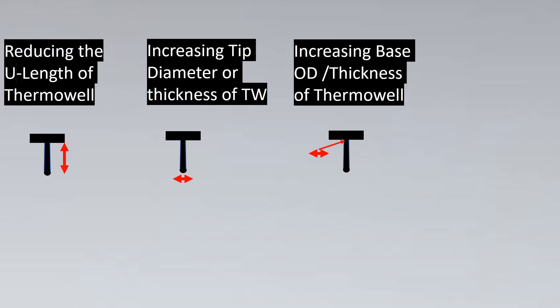This thermowell would be inserted in a nozzle, so we need to see the nozzle ID and this OD should not be so great that it's not able to fit inside the ID of the nozzle. That care we need to take, especially if the nozzle has cladding to it or the thermowell has cladding to it, and the schedule of the nozzle has to be seen.